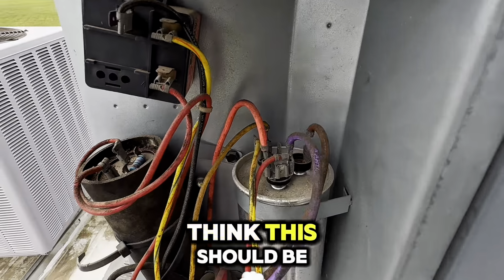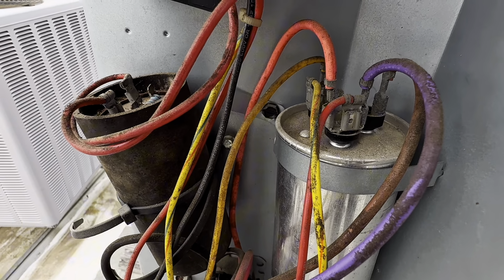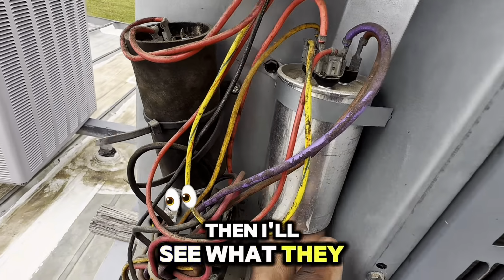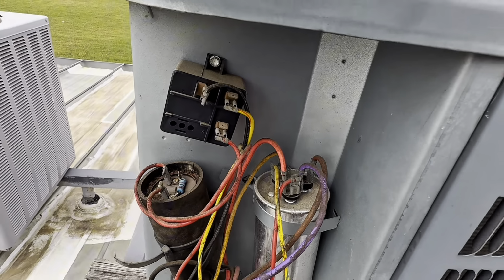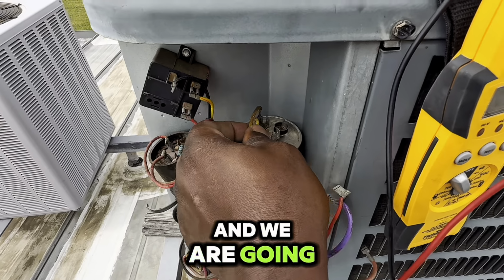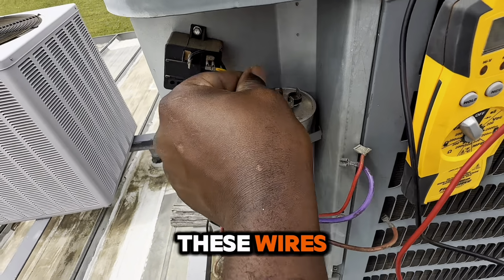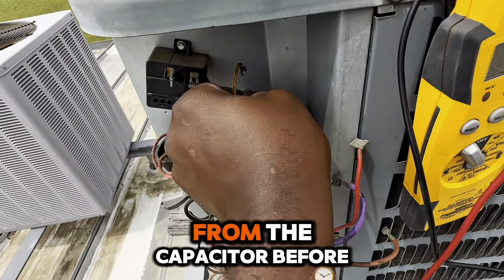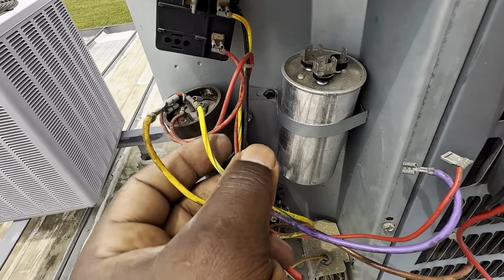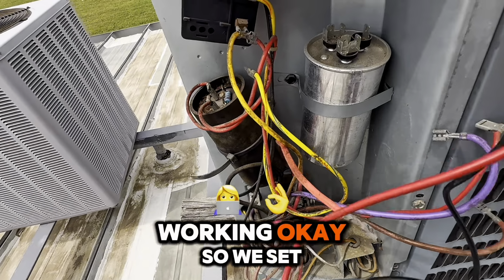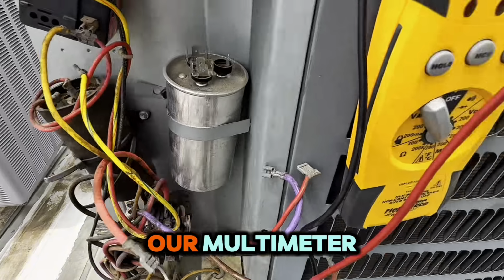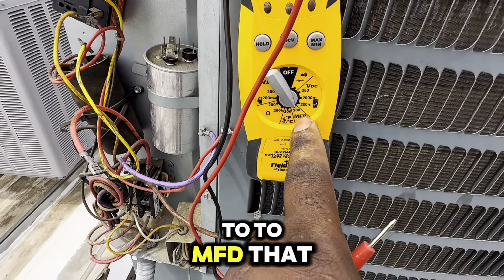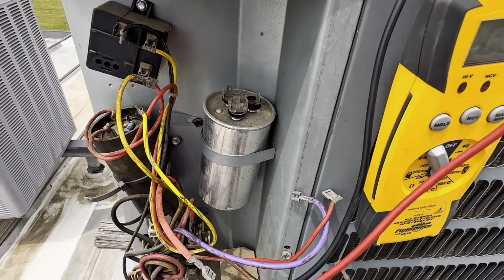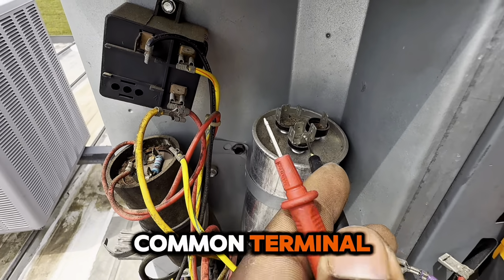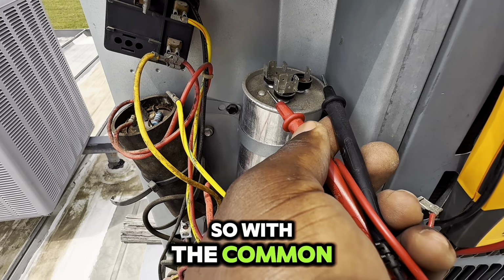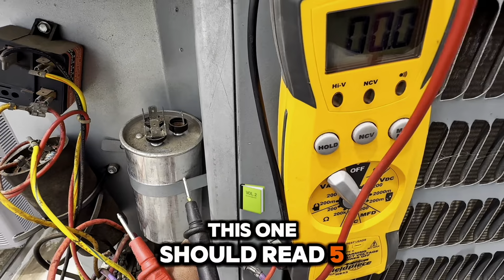Capacitor. Okay, I think this should be 5 microfarad. I'll see what they put here. Should be 5 microfarad. Take this out, and we are going to take off all these wires from the capacitor before we test if it is working. Okay, so we set our multimeter to MFD, that is for the microfarad, and this is the common terminal and this is the fan terminal. So with the common and this one should read 5 microfarad.